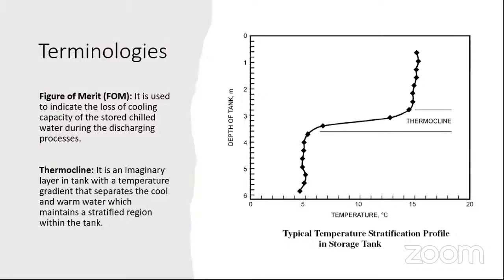Now, since this thermocline has some thickness also, let us say if my tank was a 5 meter height, and it was such that my thermocline thickness was nearly 1 meter. So my storage efficiency, so I'm not considering this thermocline as my usable chill water. So in that case, my usable chill water becomes 80% of the total tank quantity, and that is my storage efficiency. So that storage efficiency is also termed as the figure of merit.